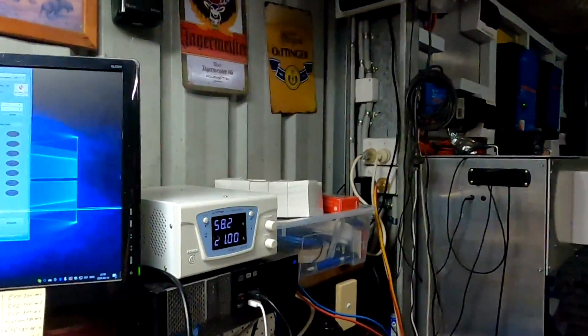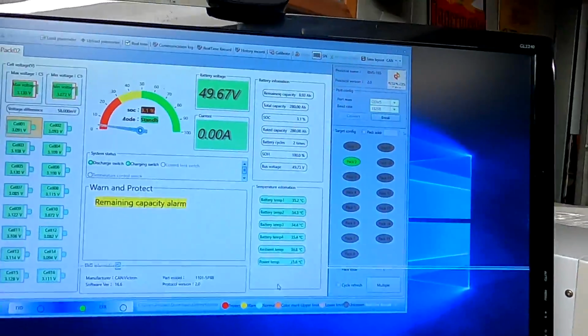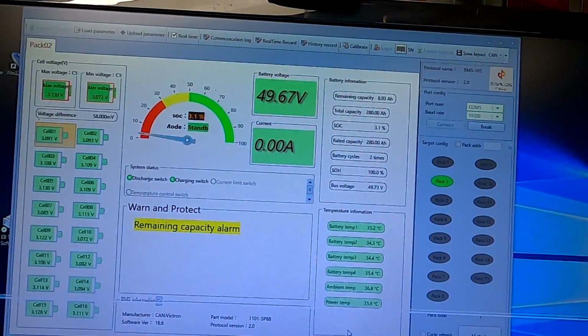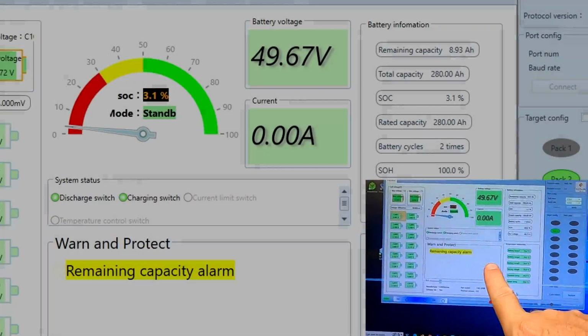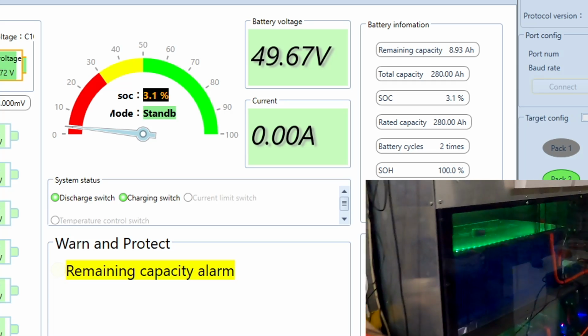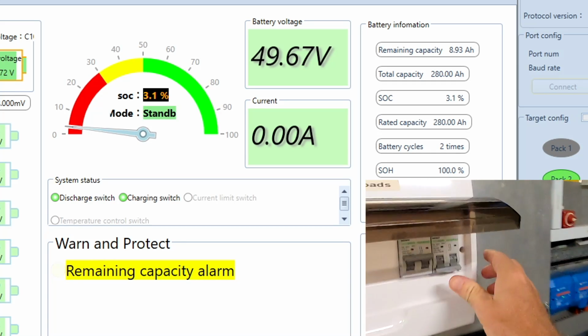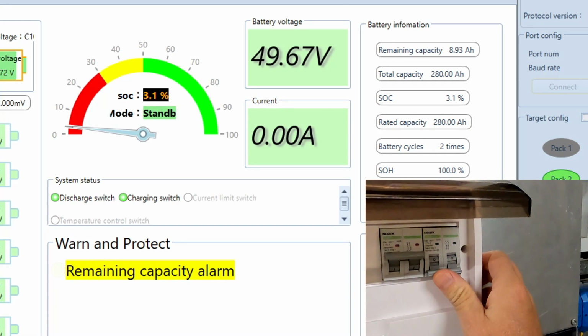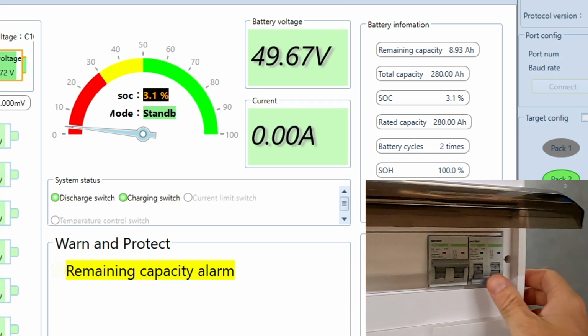If not, I have set the charge overcurrent warning in the BMS to 80 amps. If we reach this for 1-2 seconds or so, the BMS will turn off charging and activate the charge limiter, automatically limiting charging to only 10 amps. I'll leave the screen recorder running here, and we'll flick the switch now and see how many amps we actually get. Maybe it trips straight away, I don't know.